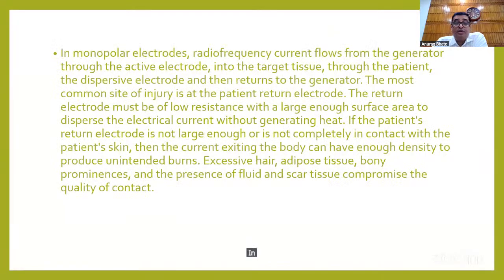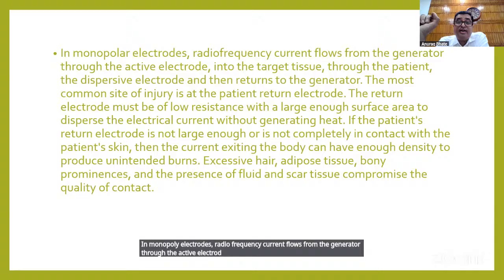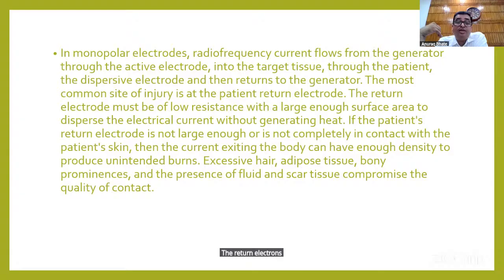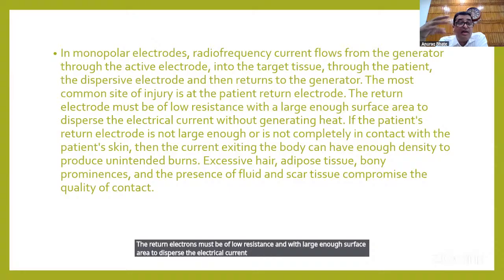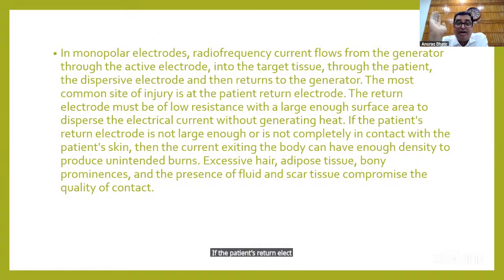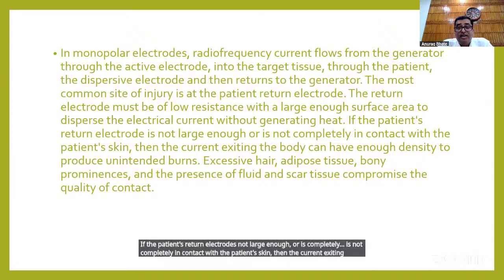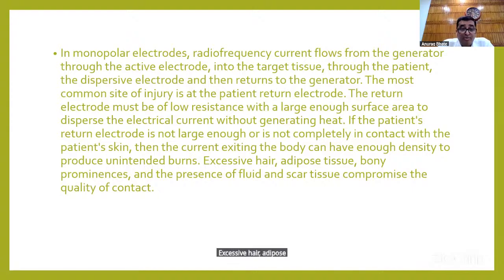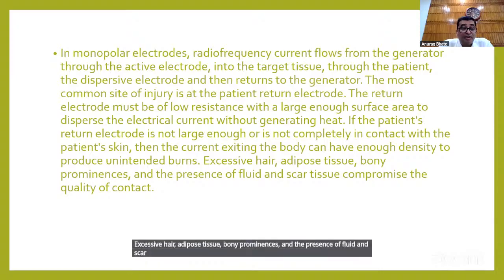In monopolar electrodes, radio frequency current flows from the generator through the active electrode into the target tissue through the patient, the dispersive electrode, and then returns to the generator. The most common site of injury is at the patient return electrode. The return electrode must be of low resistance and with large enough surface area to disperse the electrical current without generating heat. If the patient's return electrode is not large enough or is not completely in contact with the patient's skin, then the current exiting the body can have enough density to produce unintended burns. Excessive hair, adipose tissue, bony prominences, and the presence of fluid and scar tissue compromise the quality of contact.